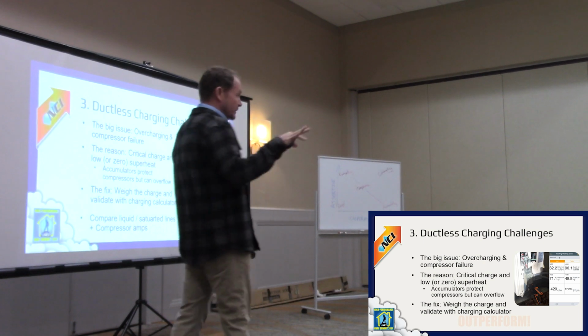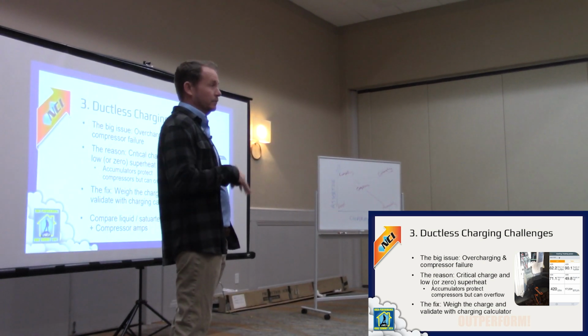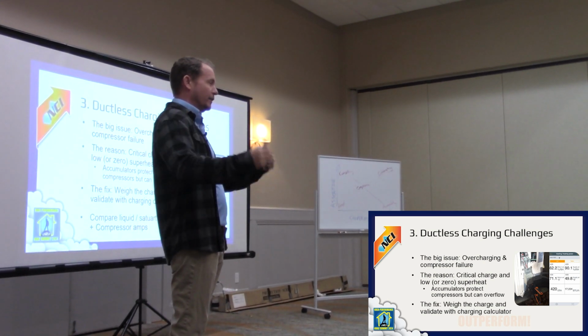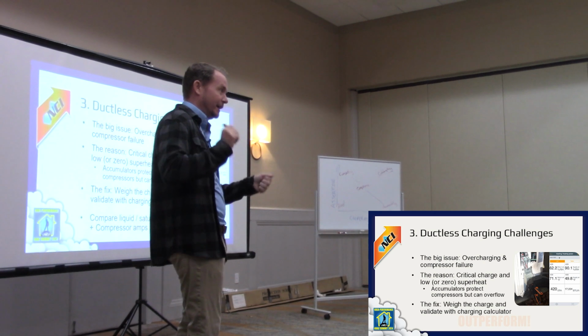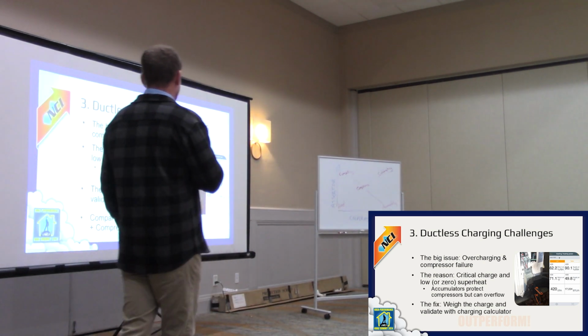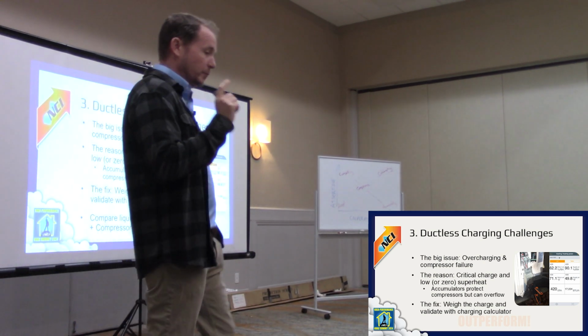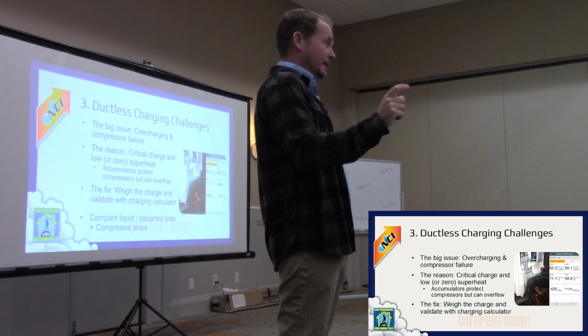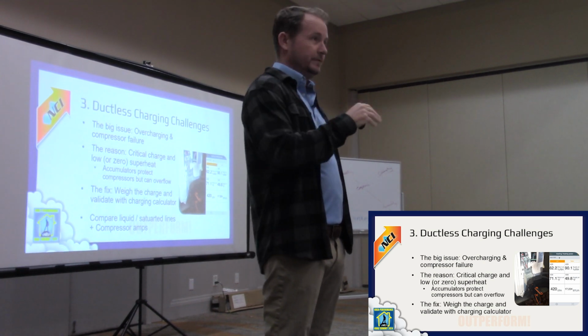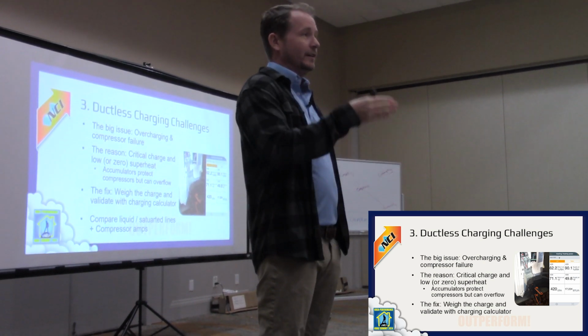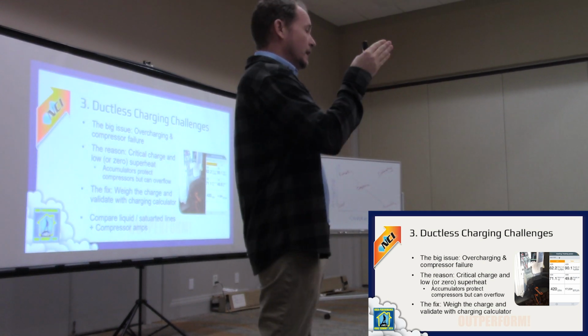In terms of your install practices, you can shave 20 minutes off because you're not doing that adding and watching thing. One thing to know is that for most ductless systems, both lines are cold lines. You know that, right? They both have to be insulated. One is a saturated line, one is a suction line.